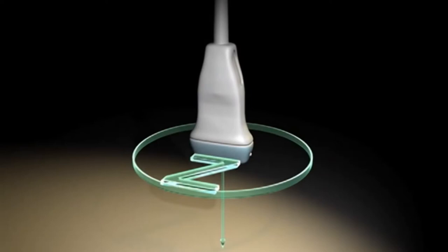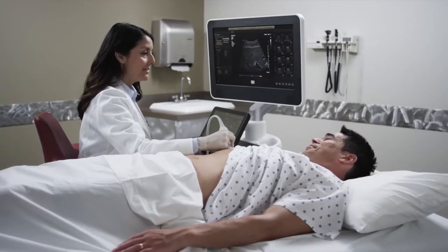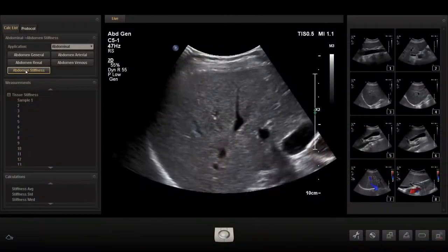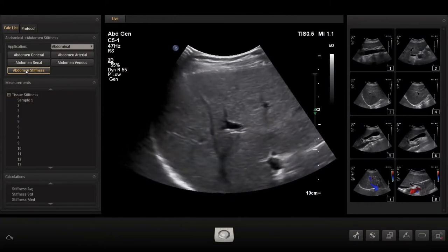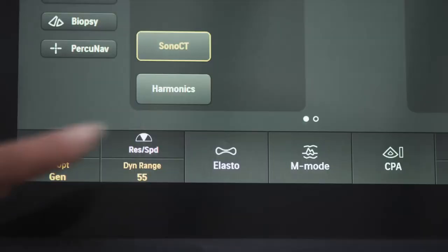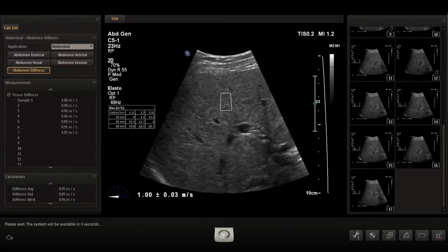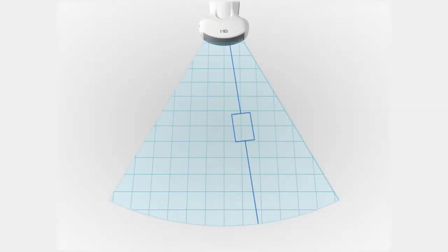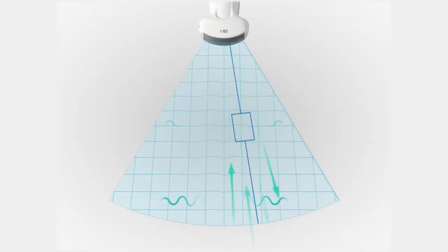Let's see about curved linear array transducers. A curved linear array scans a wider field of view because of the convex arrangement of the array elements. Curved linear or convex arrays operate in the same manner as the linear arrays, and therefore, even in this case, scan lines are directed perpendicular to the transducer face.